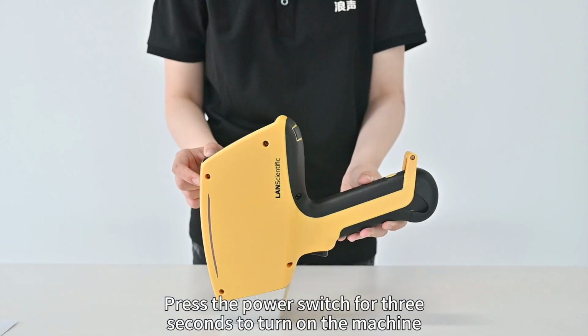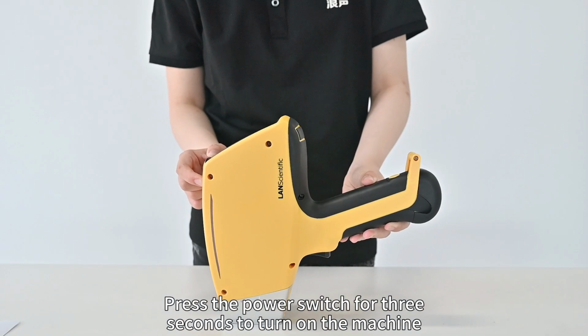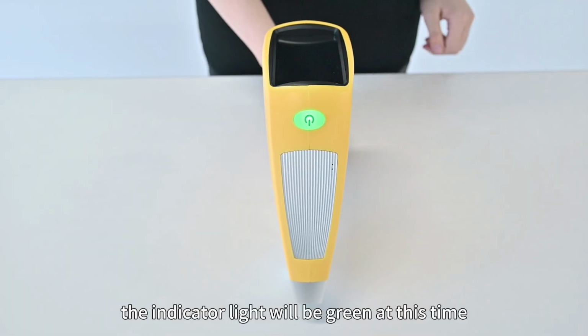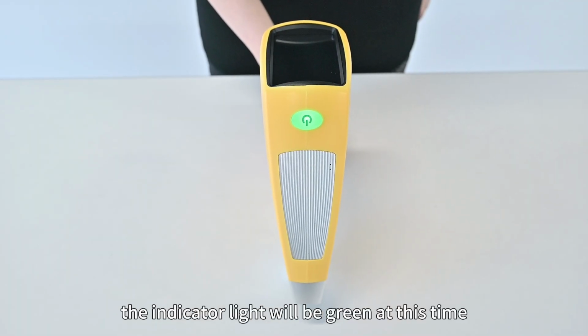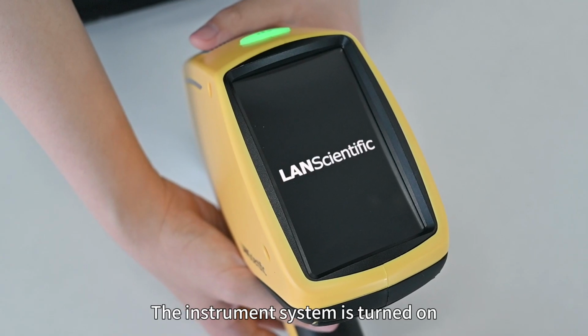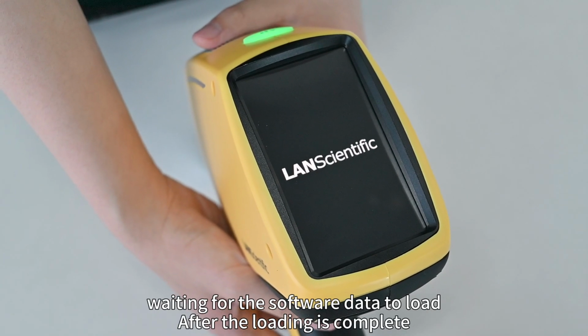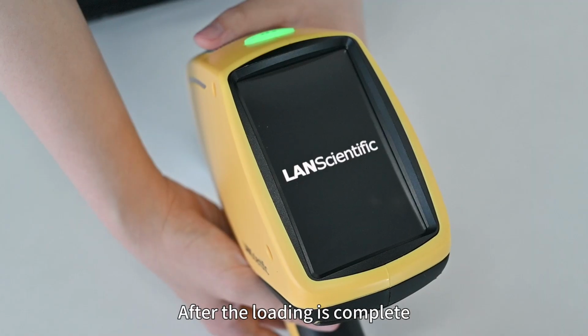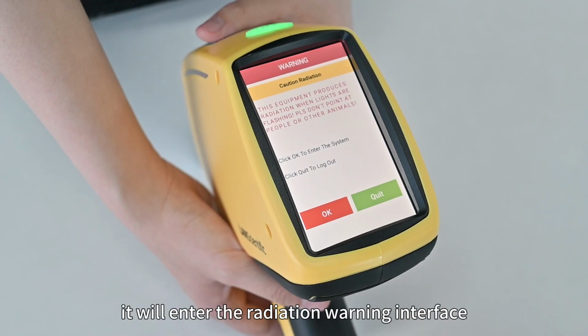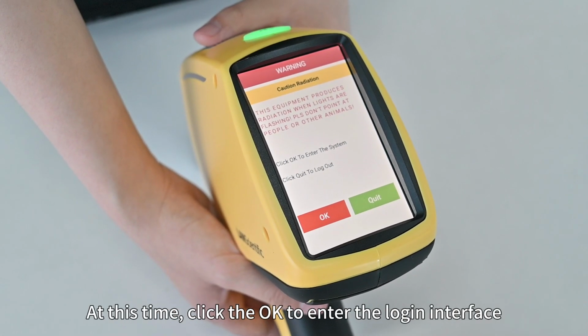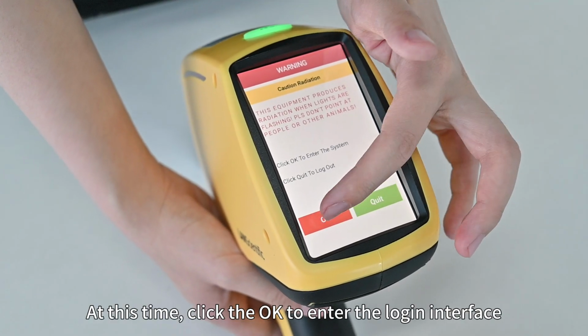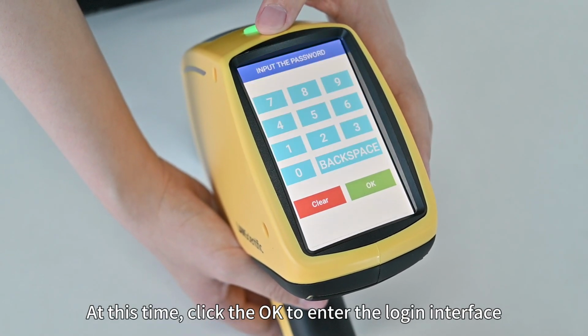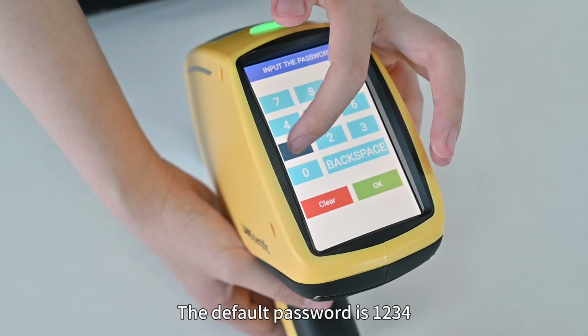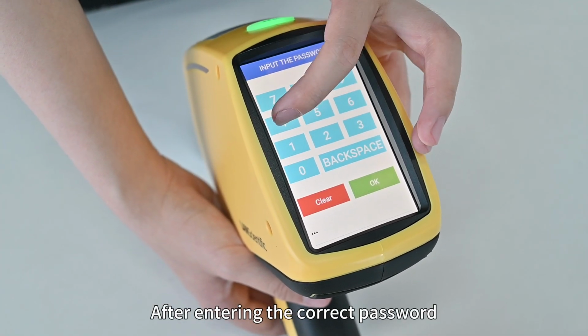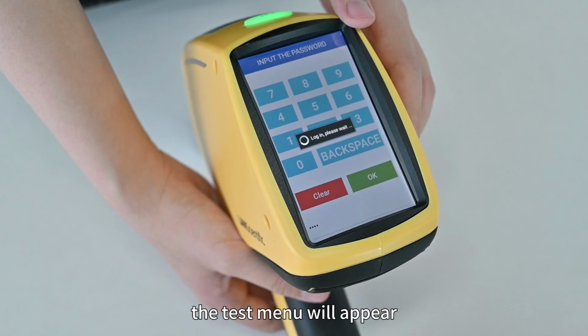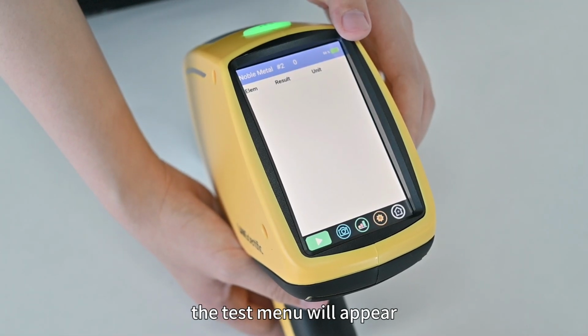Press the power switch for 3 seconds to turn on the machine. The indicator light will be green at this time. The instrument system is turned on, waiting for the software data to load. After the loading is complete, it will enter the radiation warning interface. At this time, click OK to enter the login interface. The default password is 1234. After entering the correct password, the test menu will appear.